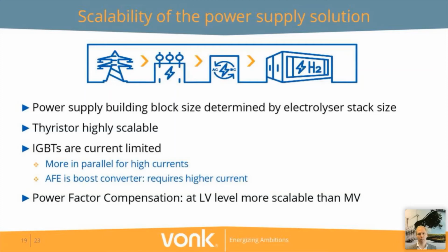Technically, this is not a problem. But commercially, IGBTs as components are more expensive anyway. So if you need to apply more in parallel, that means your prices also go up. This is even more applicable for an active front end, as this is a boost converter, and I won't go into technical details, but it means that your components are running at a higher current level. So the effect of having more components in parallel to achieve the same current level is emphasized even stronger.